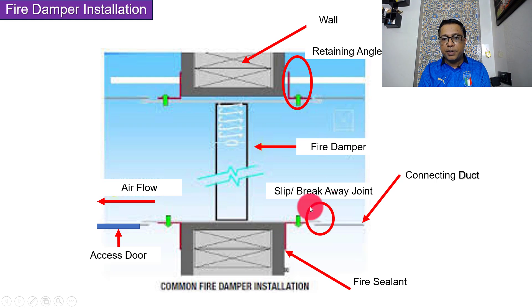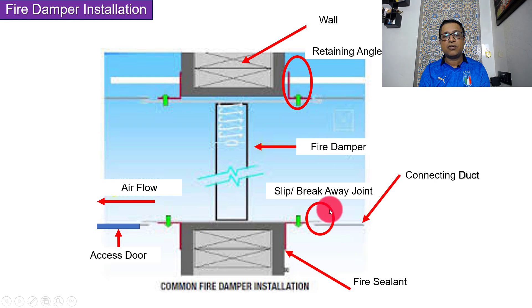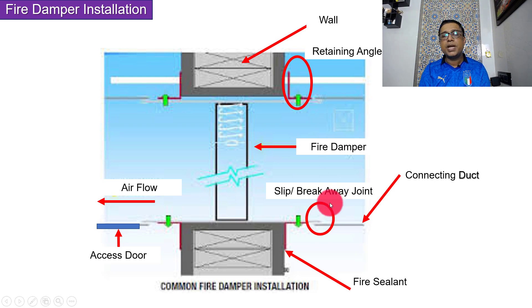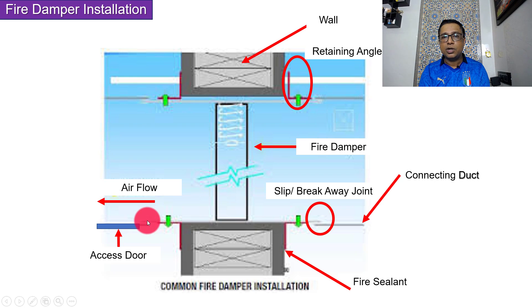This is a breakaway or slip joint — and the reason is we want the fire damper to remain intact in case of fire. If this assembly is joined very tightly, it may happen that the collapsing duct will pull the fire damper out along with it. So we need this joint to be as weak as possible without causing leakage issues. When the duct collapses, the fire damper remains intact.